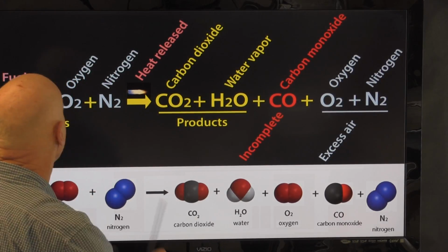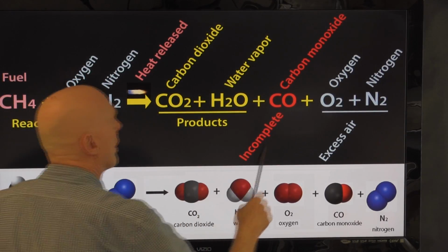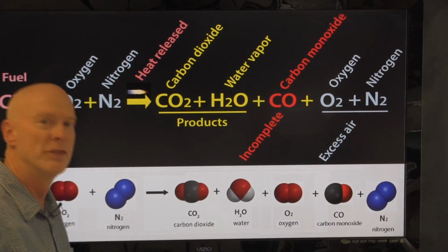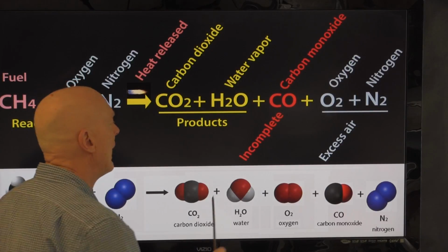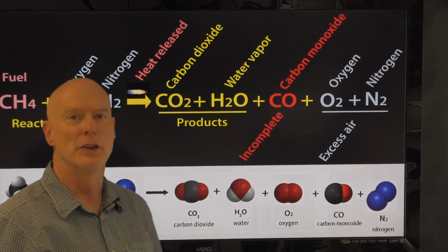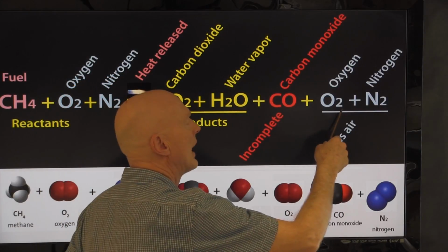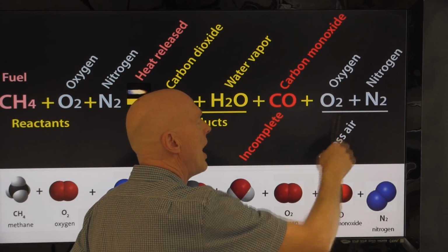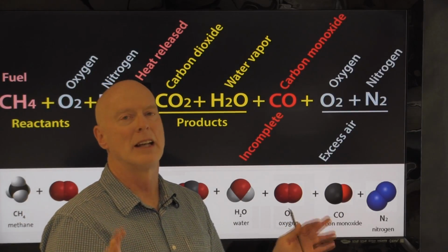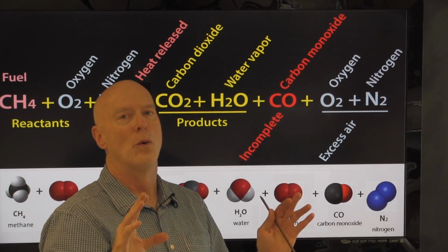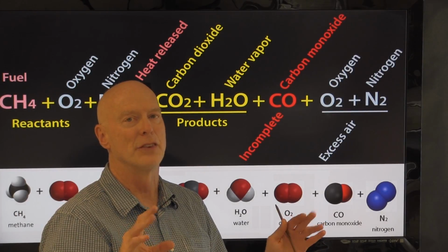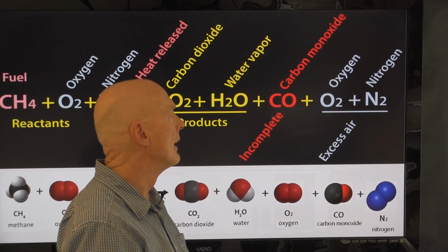So in the safety part of the equation, we're looking for carbon monoxide. That's a red flag for us. And we measure it in the undiluted flue gases, but the undiluted flue gases still have some oxygen in it. And some people think that we need to calculate what the CO would be without any air, and that's the air-free CO.